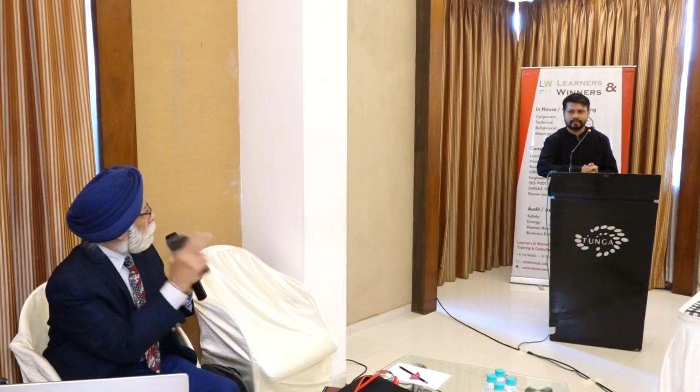I did not see any marking of an arc flash zone and a clear green zone, when you are talking of regular equipment going off and on and taking regular monitoring of the data. It should be in a green zone, but it does not seem to be. Maybe your substation is very old and that much space is not there. So I strongly feel you should hang it from the top through a monorail, so that this problem is also sorted out, and wherever it has to come, it drops down. Again, after taking the reading, it goes up and gets locked at the end. Think over it.